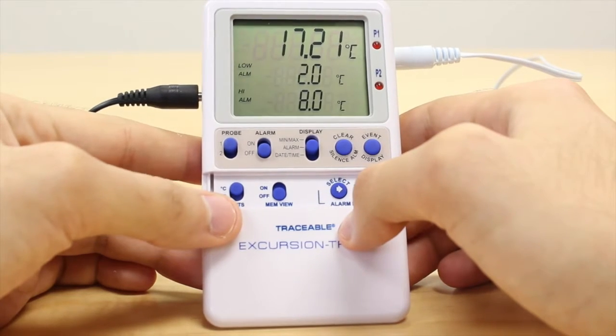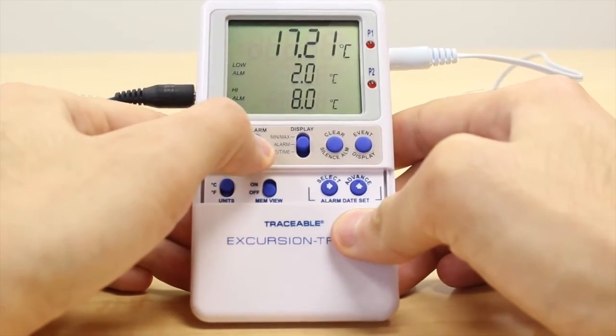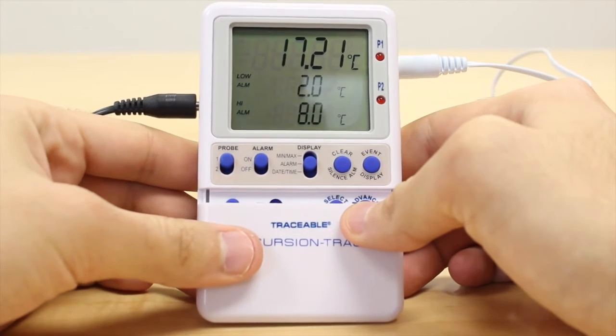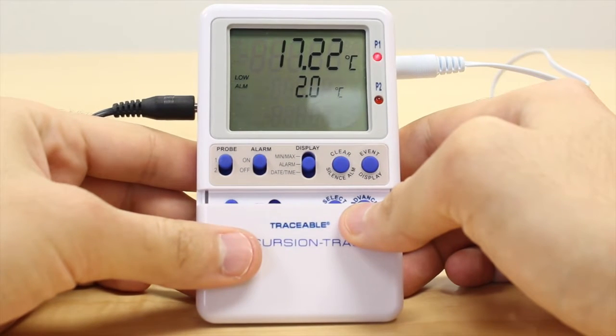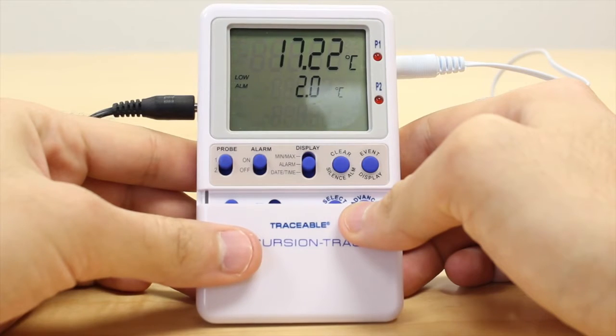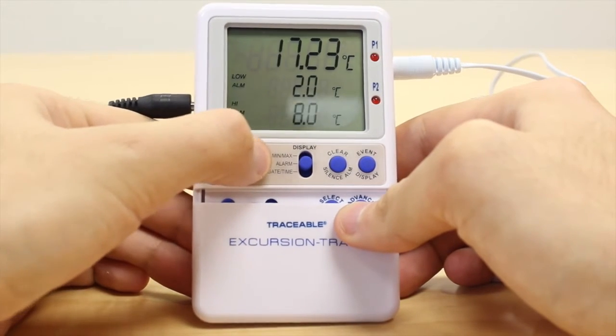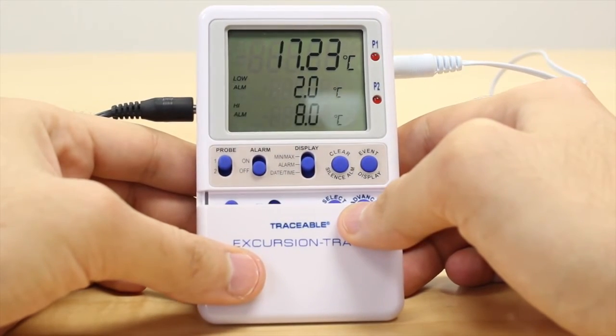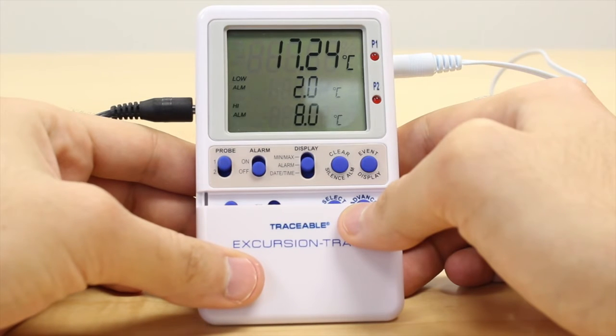Now that you're done, remember to turn the alarm on by setting the lever to on. If you're currently setting this in a room temperature environment, it should alarm indicating the alarm is working properly. For now, turn the alarm off and place your probe 1 in the desired environment. Once the temperature reaches in between the low and high alarm, then activate your alarm again.